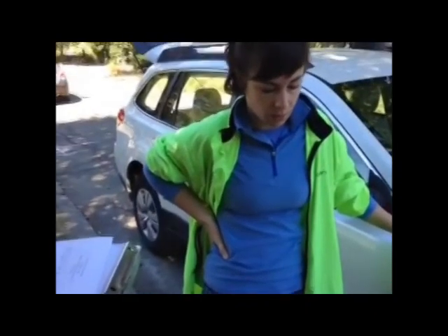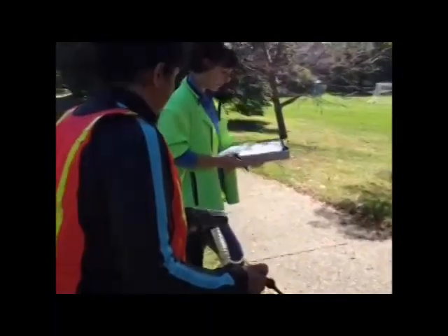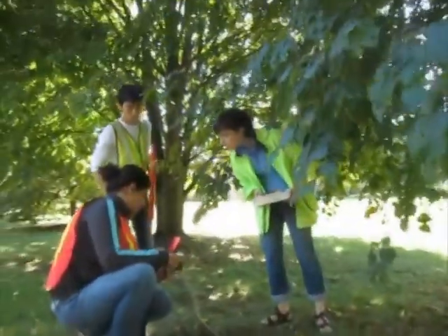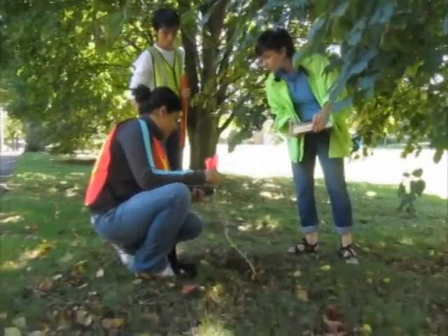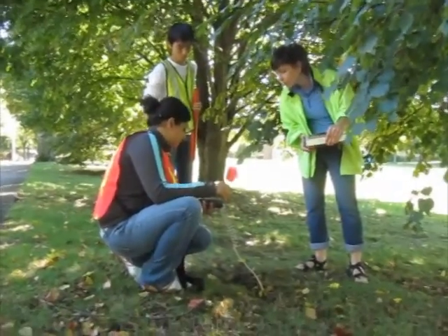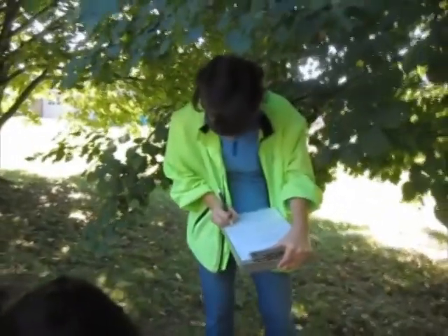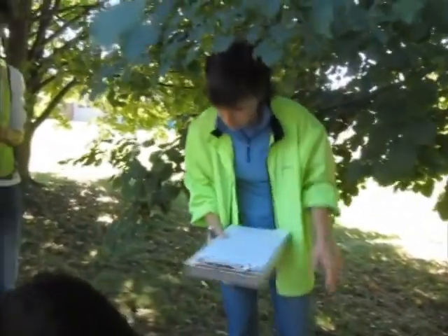You think you'll stop at what? When it's down to, initially we had 10% or 5%? We agreed on 0.25% gas. So it may take walking a long way. Yep. We have constrained it. Now you know where the high point of a very long leak here on Pine Grove is. Yeah, so we need to figure out what that threshold is.